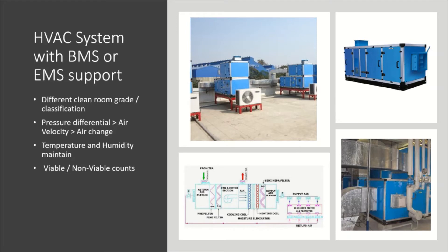In this presentation, we will discuss the area classification and associated controls involved in injectable manufacturing. Let's begin with the HVAC system. When we talk about cleanroom controls and management, HVAC is the most important system. It helps to maintain the cleanroom classification including pressure differential, air velocity, air changes per hour (ACpH), temperature, and humidity.